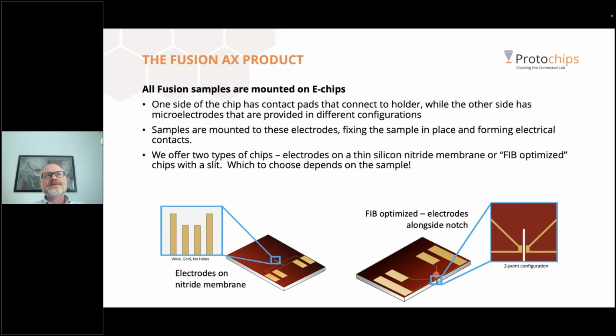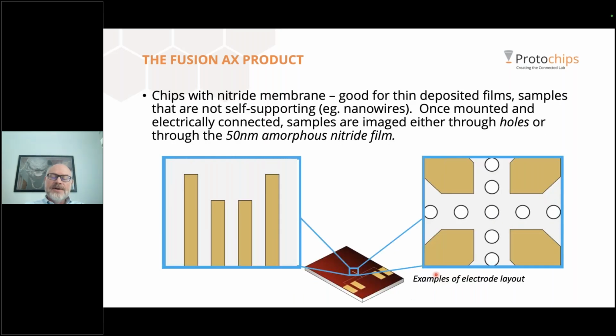And which you want to choose depends on the type of sample that you want to analyze. Now, chips with a nitride membrane, like shown here, should be chosen for samples that are not self-supporting and need the nitride film underneath as a support. Examples of these types of samples would include thin deposited films that need to be deposited on a substrate, or small fragile samples like nanowires. These samples are imaged either through the 50 nanometer thick nitride film or through small holes that are patterned in the nitride. And we'll take a look at an example of that type of analysis in a moment.